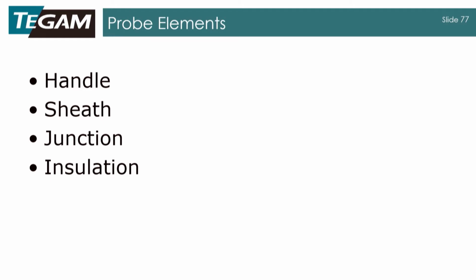Insulation. Now there's a few different places that you're going to run into insulation. One is the insulation around your thermocouple wire, and then also we're going to talk about the insulation for your actual cable that runs from the probe to your instrument. And that's included there in cable. And then lastly, we're going to talk about different types of connectors and what connectors are used for what types of temperature probe types and for their instruments.